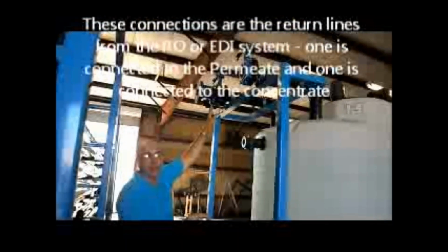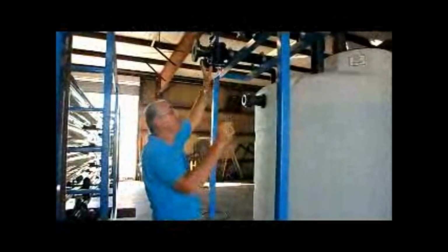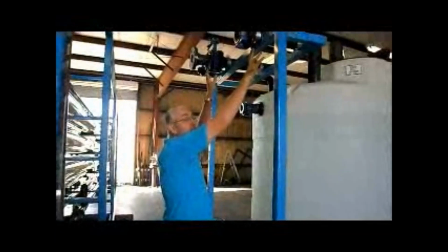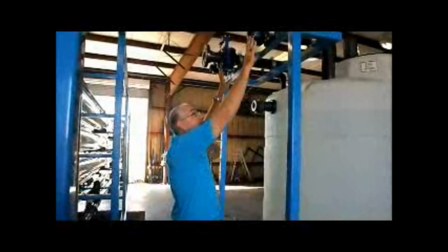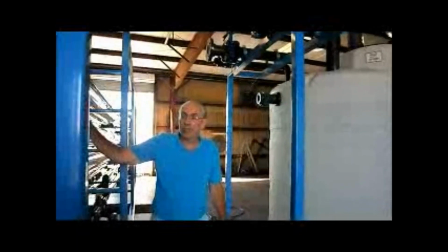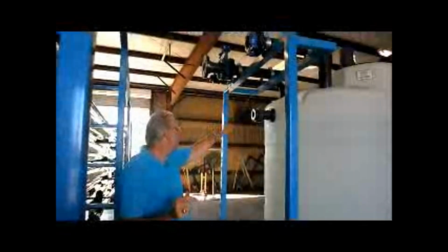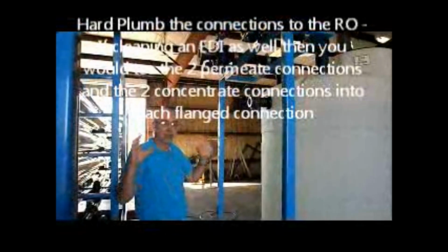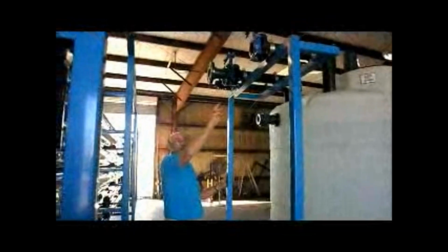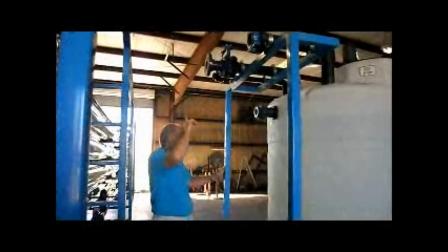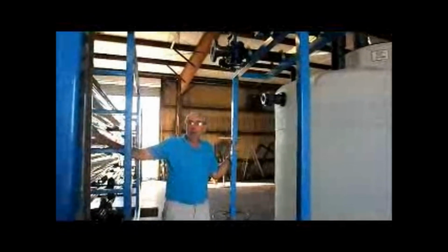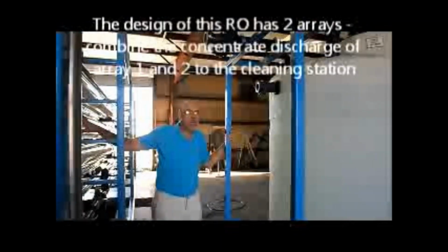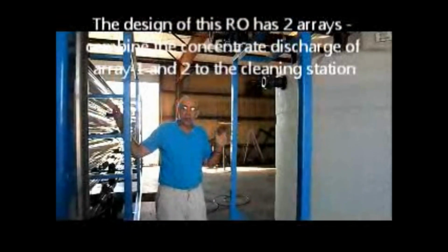So then we have these 2 primary connections right here. These are the return lines from the RO skid and EDI skid. One of them is from the concentrate, one of them is from the permeate. So you will run pipes from this to the permeate outlet cleaning connection on the RO and also to the permeate outlet connection on the EDI. Both of those will tee together and come here. Same for the concentrate. You actually have to make 3 connections for the concentrate: 1 to the EDI, 1 to the array 1 concentrate outlet for the RO, 1 to the array 2 concentrate outlet from the RO. Those 3 should all be teed together and brought back to this pipe.